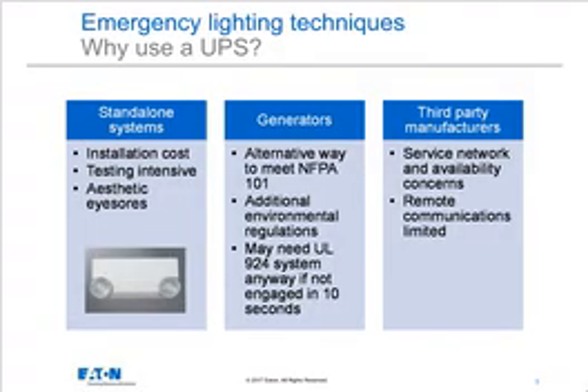Why use a UPS for emergency lighting? If you're familiar at all with this, you're used to seeing the little white or beige or dark boxes on the wall that have a couple of lamps on them, and they light up automatically when utility power fails so that I can see to exit the building, navigate dark hallways, and find the proper way to the exit. And it's not just the hallway lights and those types of emergency lights, but also the illuminated exit signs that basically are showing me how to get safely out of the building through multiple pathways if I need to during a power-related emergency.